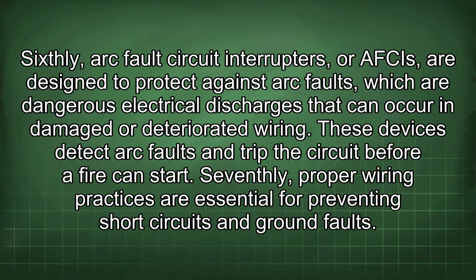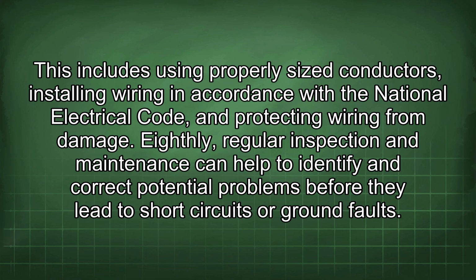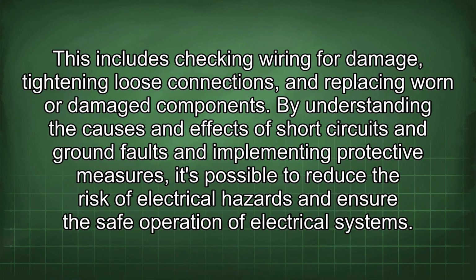Sixthly, arc fault circuit interrupters, or AFCIs, are designed to protect against arc faults, which are dangerous electrical discharges that can occur in damaged or deteriorated wiring. These devices detect arc faults and trip the circuit before a fire can start. Seventhly, proper wiring practices are essential for preventing short circuits and ground faults. This includes using properly sized conductors, installing wiring in accordance with the National Electrical Code, and protecting wiring from damage. Eighthly, regular inspection and maintenance can help to identify and correct potential problems before they lead to short circuits or ground faults. This includes checking wiring for damage, tightening loose connections, and replacing worn or damaged components. By understanding the causes and effects of short circuits and ground faults and implementing protective measures, it's possible to reduce the risk of electrical hazards and ensure the safe operation of electrical systems.